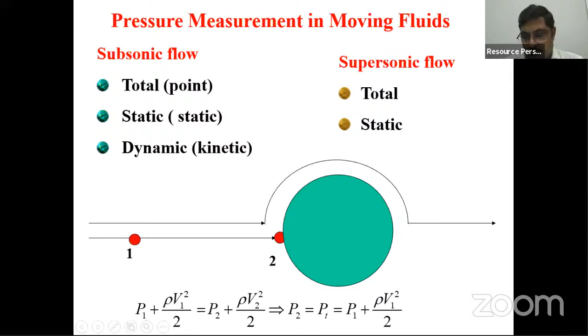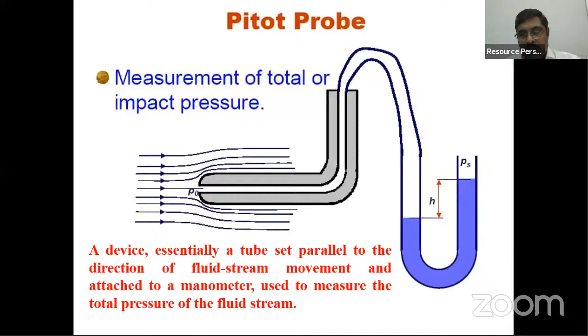Anyway, here this is a pitot tube. It's a very simple instrument, meant for measuring the stagnation pressure or the total pressure. You see here there is a capillary. This capillary opening is kept just opposite to the flow direction, so that the flow will directly impinge into the capillary. The capillary is connected to a manometer. So the total pressure, or the stagnation pressure, experienced by the fluid will be communicated to the manometer. By measuring the fluid displacement in the manometer, you can measure the total pressure. This is the stagnation pressure.